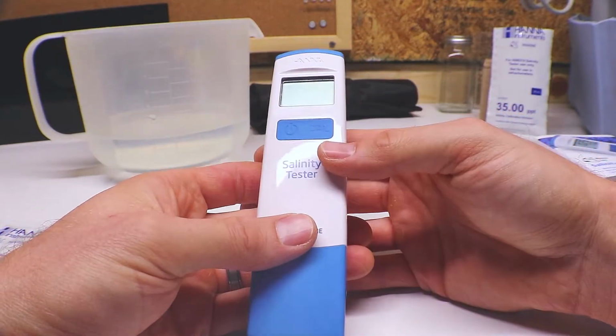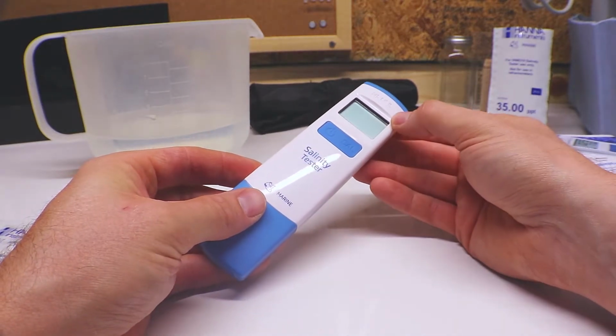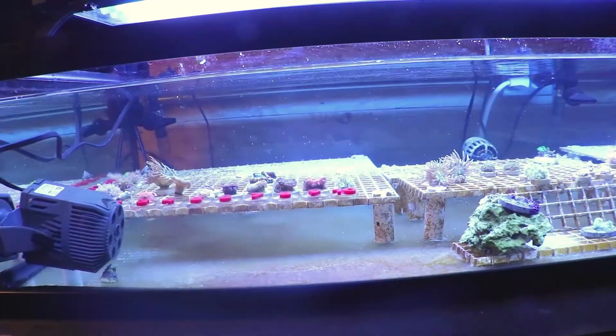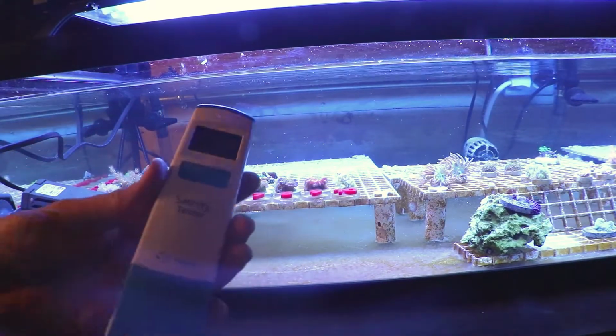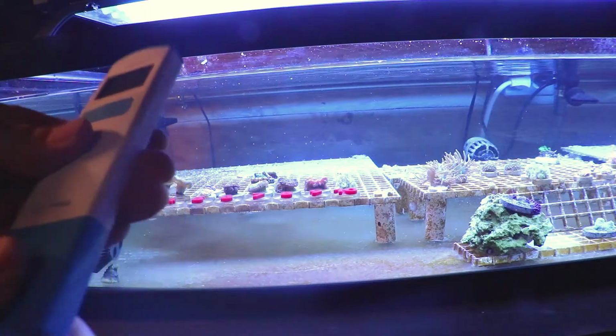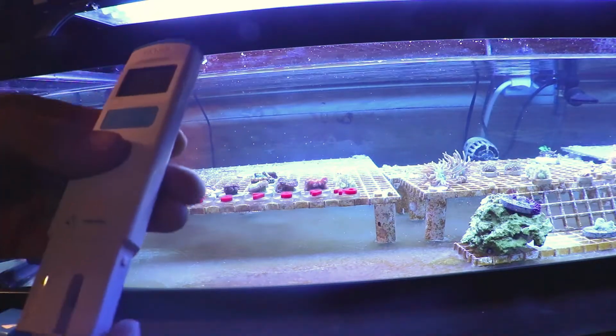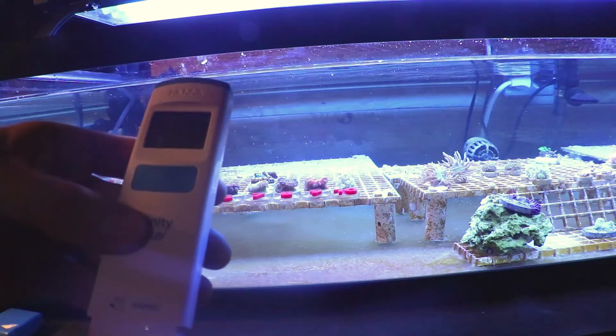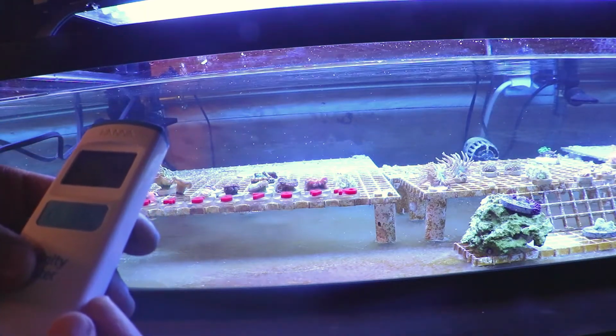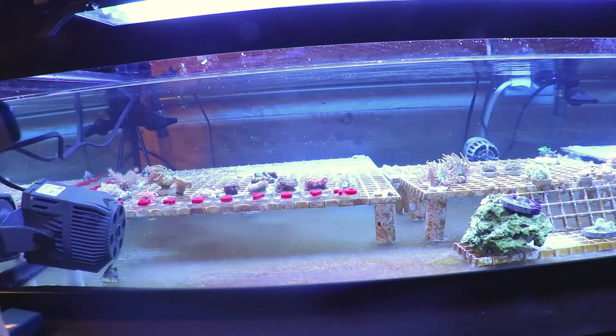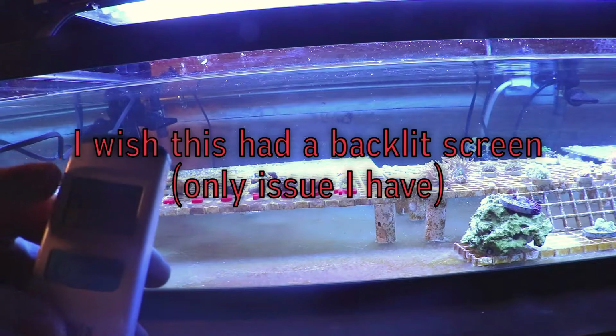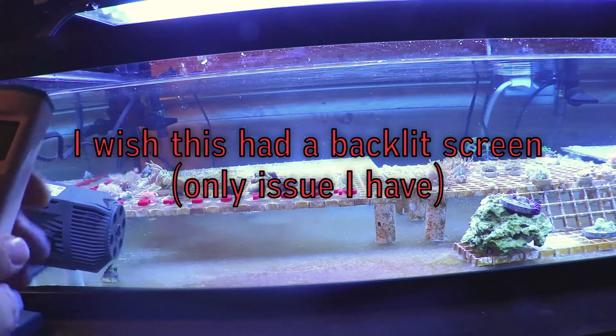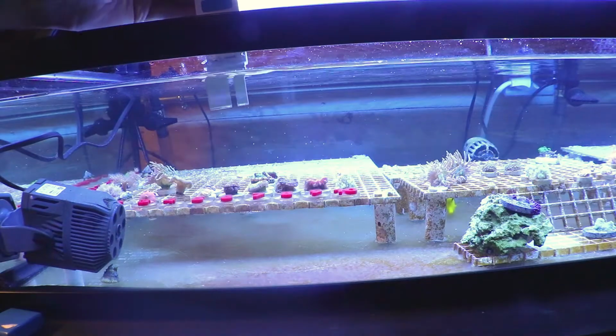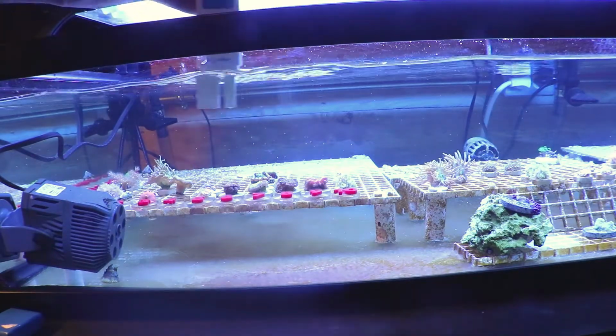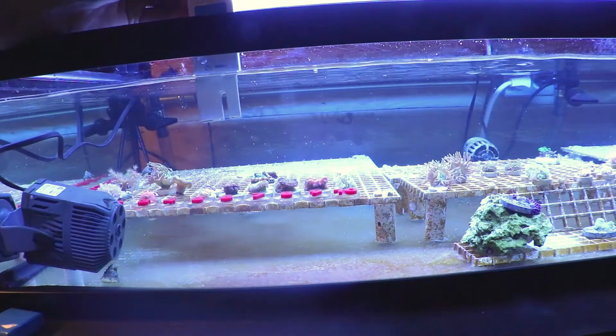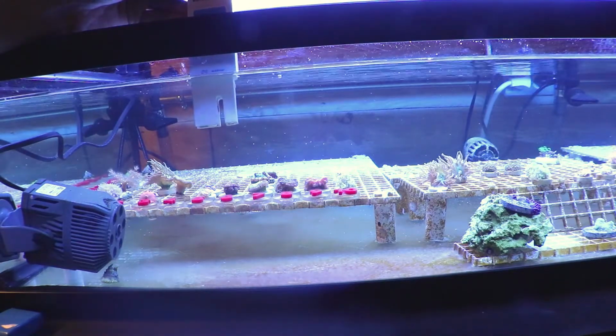So we'll go over here to one of the frag tanks and I will show you how to test with it. Okay, so we are calibrated. We are ready to test. We will turn the unit on. Okay. It's got our hourglass blinking up here in the corner saying that it's ready to test. So all you do, put the probe in the water, and the directions say to give it a couple of swirls to dislodge any air bubbles. And our hourglass is blinking on the left here.